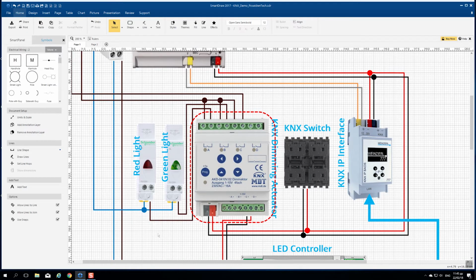One KNX dimming actuator. This dimming actuator is from MDT and I'm using it for this demo due to its small size. It can control up to 4 1 to 10 volt devices such as LED stripes, RGB or RGB white LED stripes, and can also be used as a switch actuator.